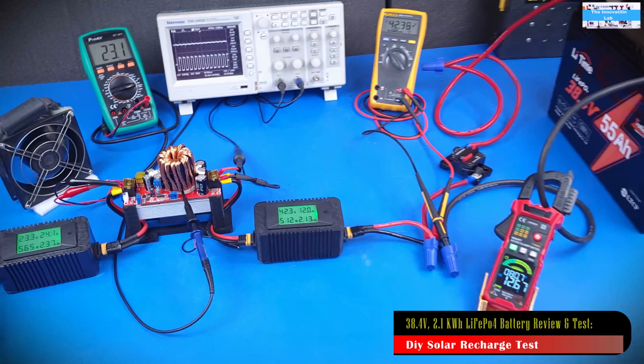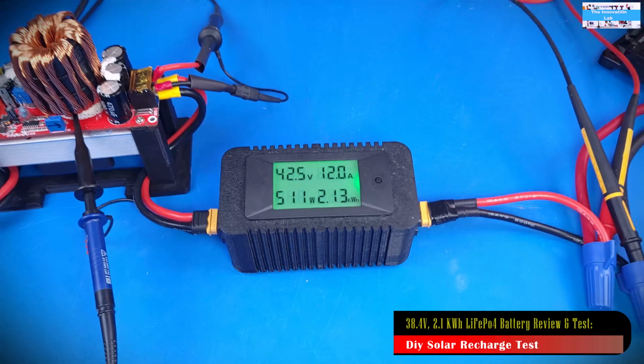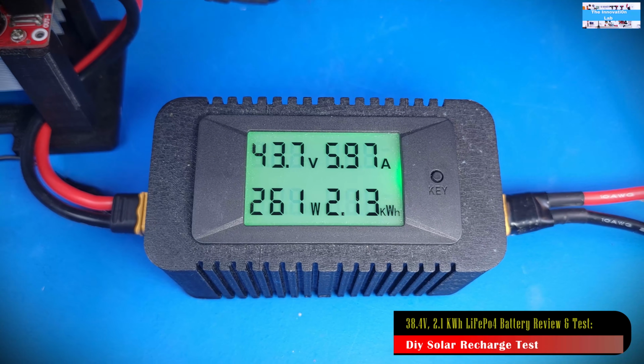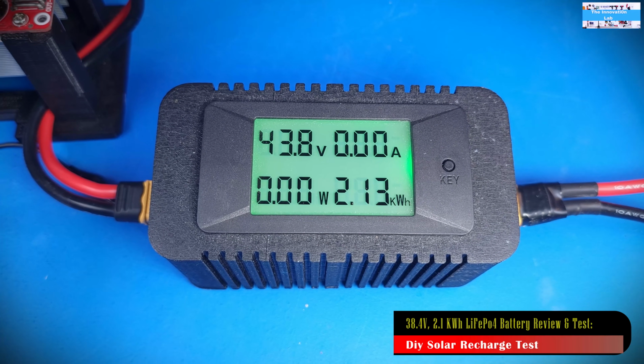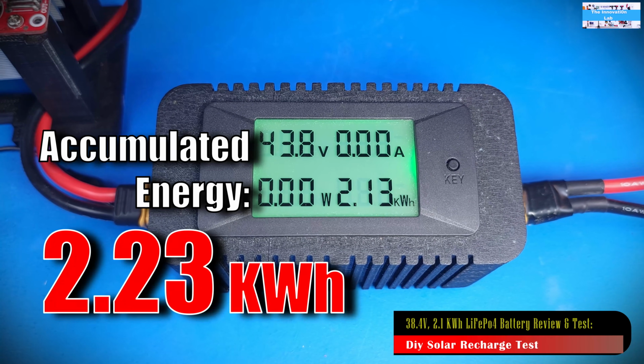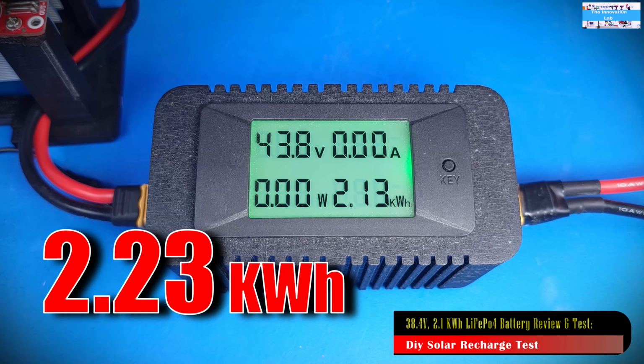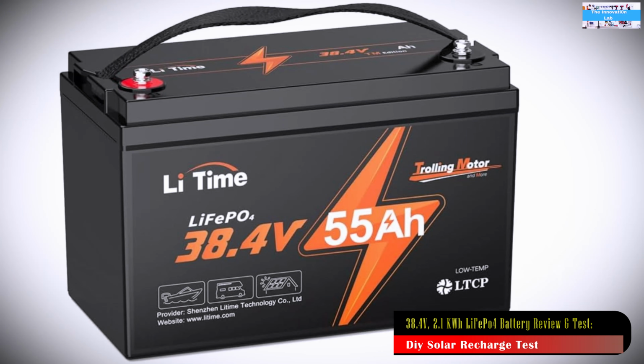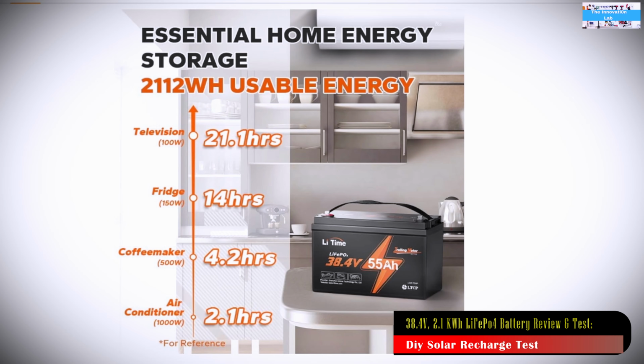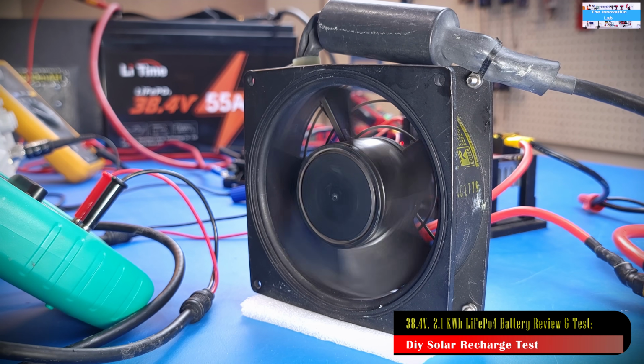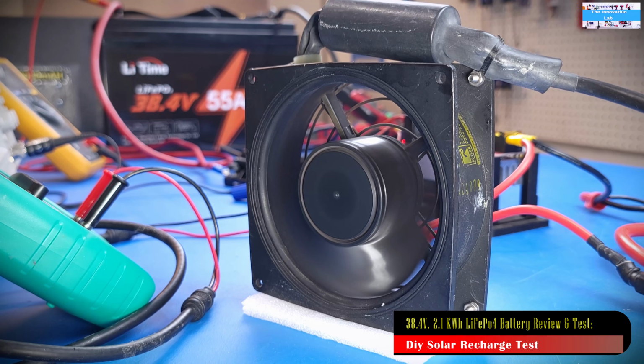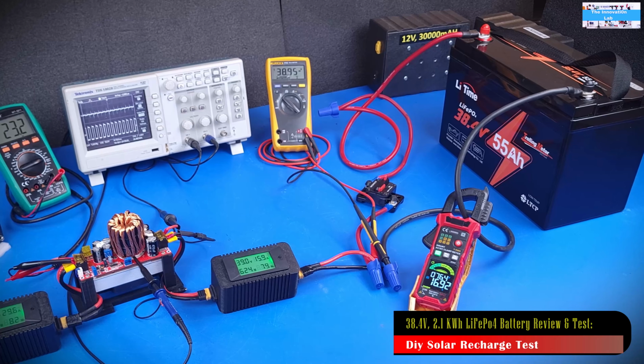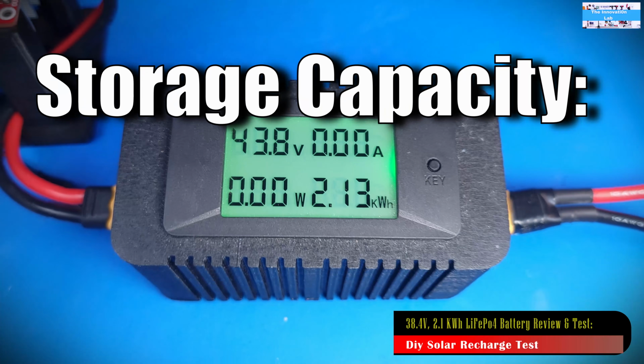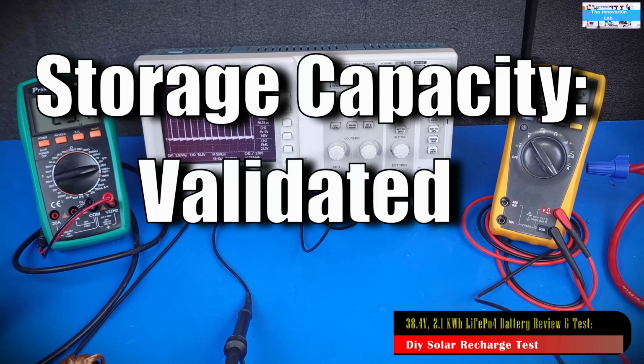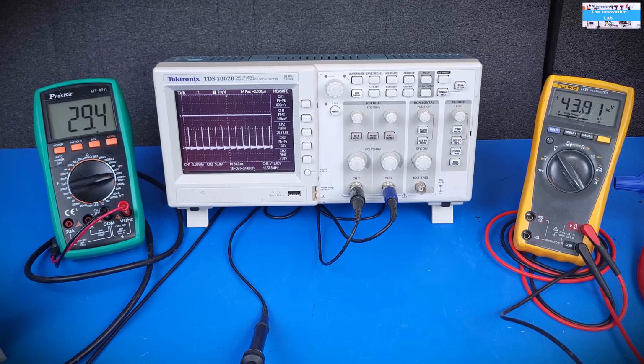Finally, looking at the overall accumulated energy in watt hours, accounting for a 5% correction factor, we saw that this battery was able to store about 2.236 kilowatt hours of pure solar energy from the solar panels, which is amazing. This validates the storage capacity rating of this battery of 2.112 kilowatt hours - we actually exceeded it here, which is amazing. This test has given us another way to validate the specifications of this battery, and the battery solar energy storage performance was great.